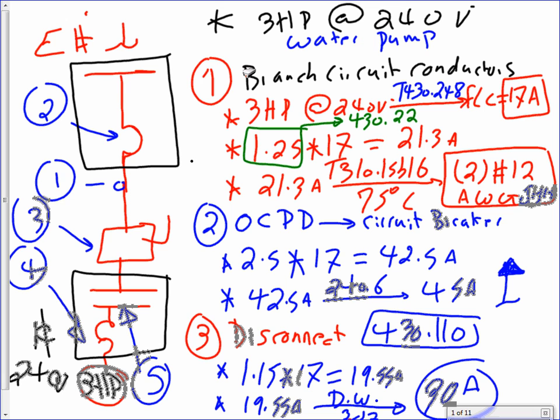I sized the overcurrent protection device, the conductor, the disconnect, the controller, the overload for a motor. Done. I can change this one into a 10 horsepower motor and nothing will change. You just change the numbers; the numbers will change. The process continues to be the same.